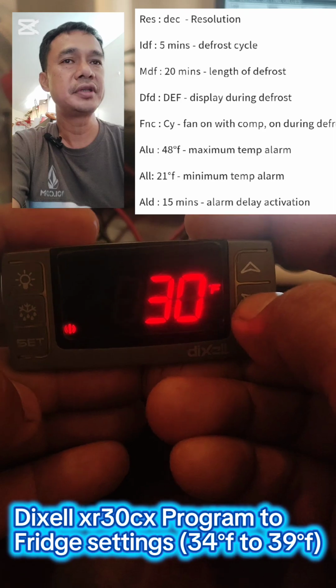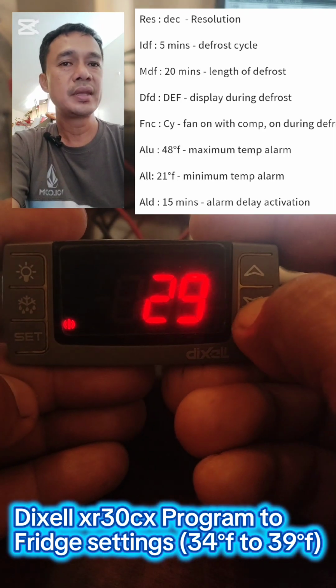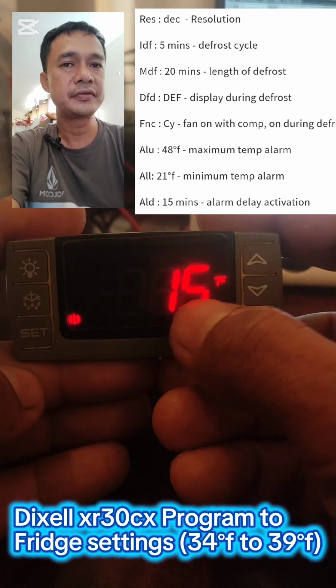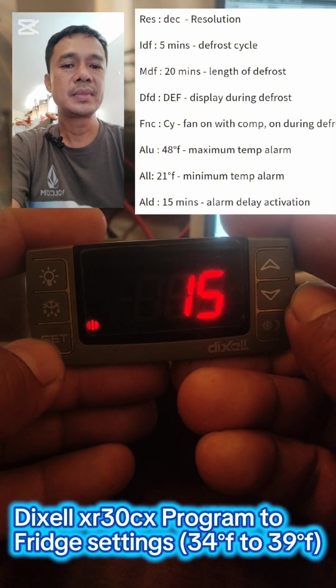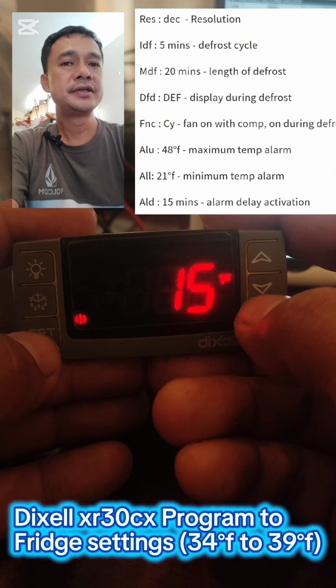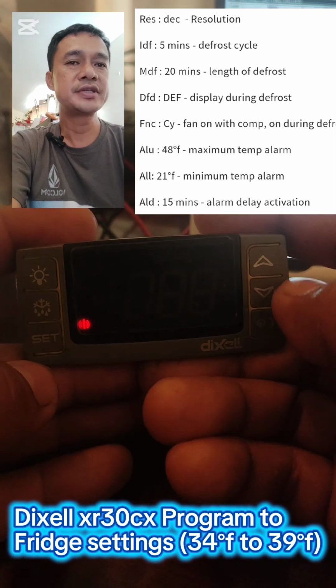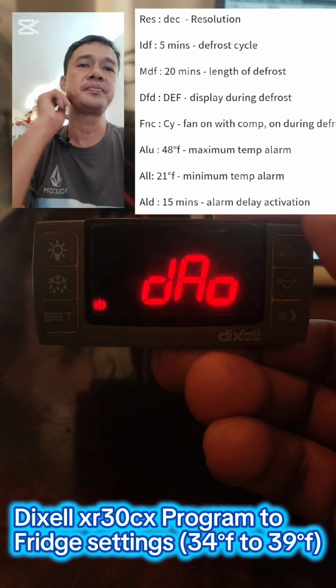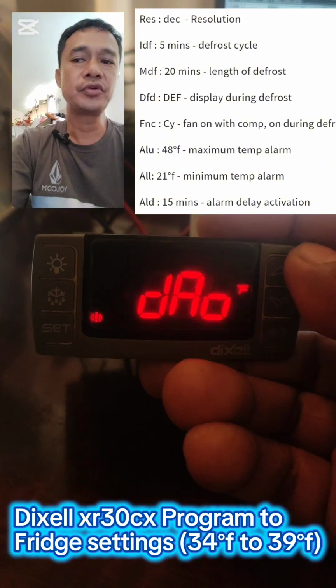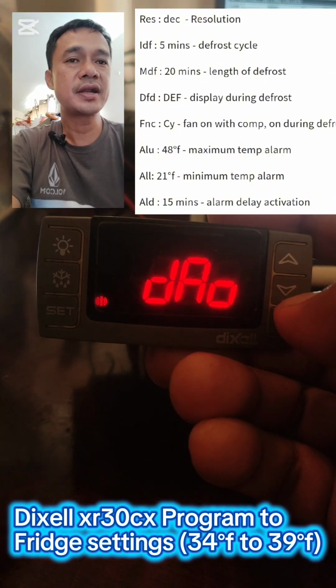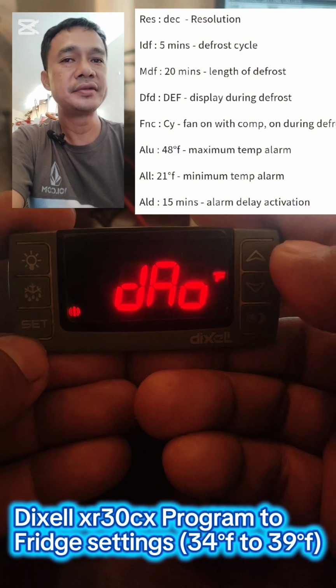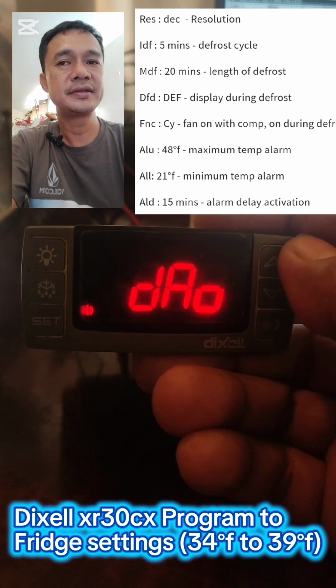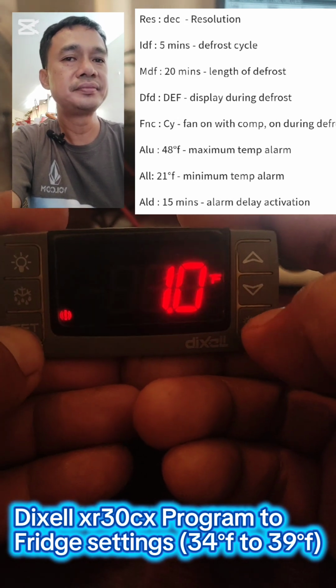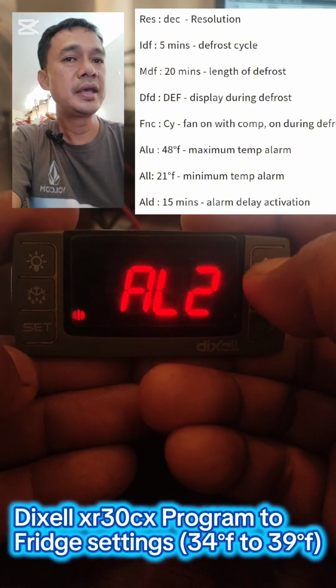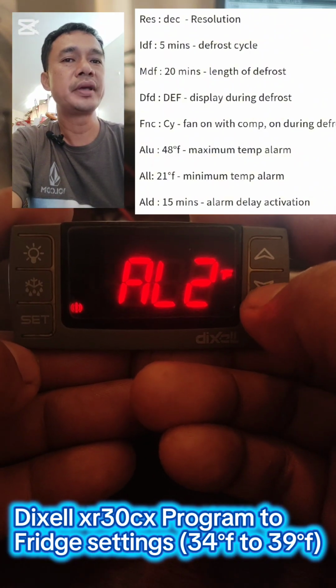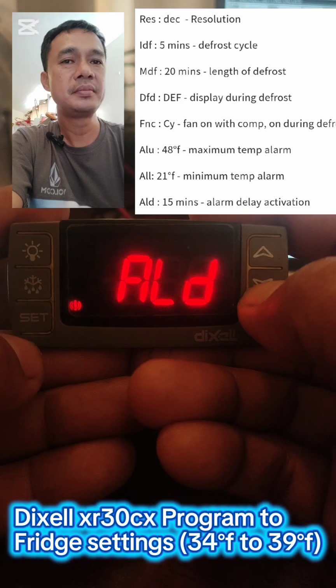The default for this is 120. And I want that to be activated after 15 minutes. For example, we have ice formation. Temperature is going up. Once it reads 48 degrees Fahrenheit, then it counts 15 minutes. After those 15 minutes, a high temperature alarm will show up, and that alarm is HA.